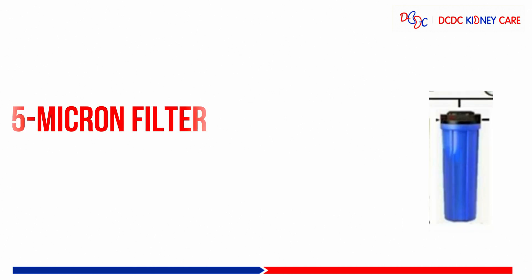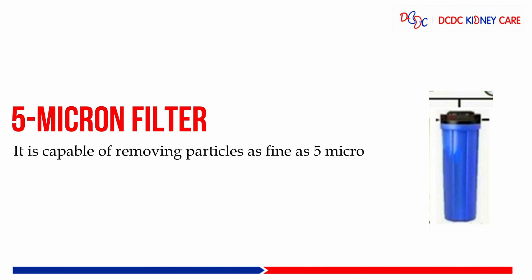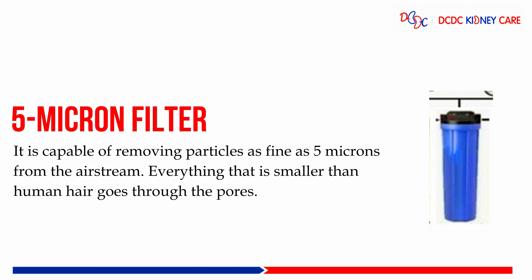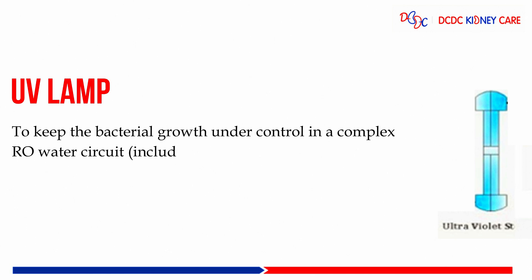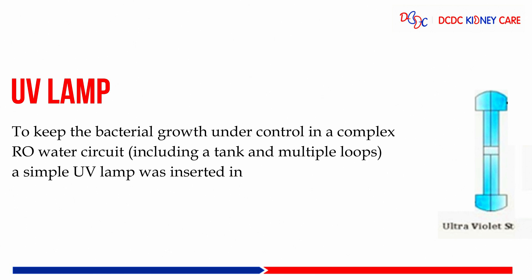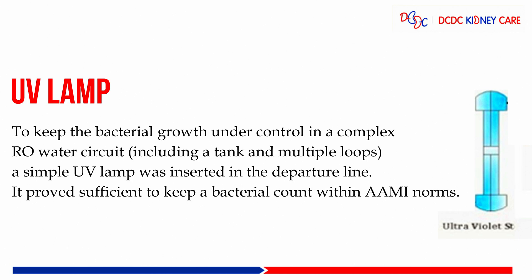Then a 5 micron filter, capable of removing particles as fine as 5 microns. Then UV light and UV lamp, used to keep bacterial growth under control in a complex RO water circuit including the tank and multiple loops. A UV lamp is inserted in the departure line.